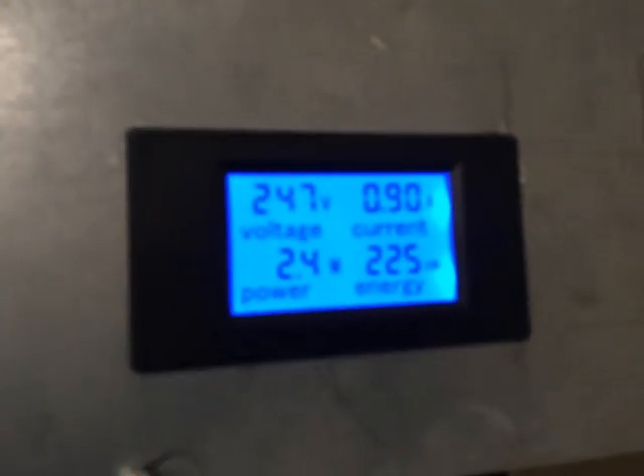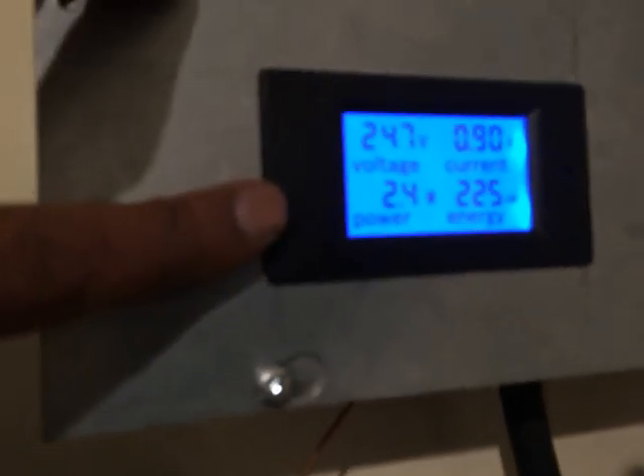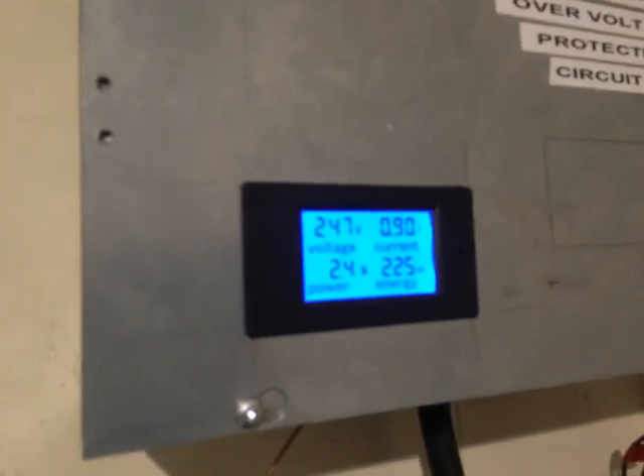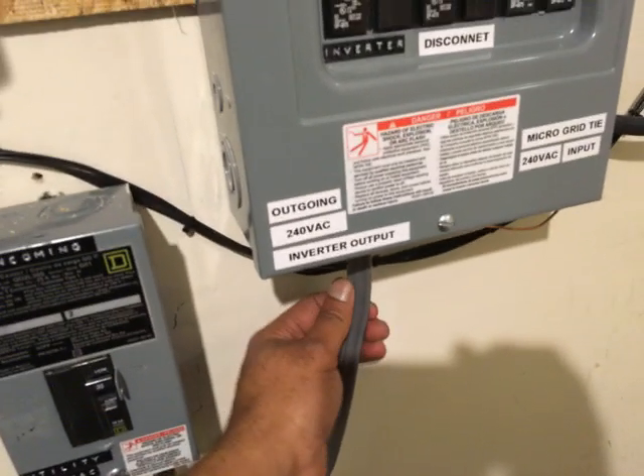Anyway, this is my new setup - I essentially just changed it. I also wanted to show folks what it means to have anti-islanding with your grid-tie inverter, to have a certified grid-tie inverter, and also to re-emphasize what I was saying in an earlier video. As you can see, I've got 247 volts at 0.9 amps and 24 watts coming from somewhere - and I believe it's the synchronization between the grid-tie inverter and the inverter charger. This right here is the output side of the inverter charger.